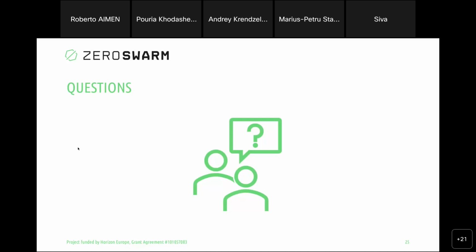Siva has a question. Just a quick thing. We have different types of industrial Ethernet protocols like Class A, Class B, Class C. For example, Class A, like EtherNet/IP, makes use of the whole 5-layer or 7-layer model, all the stacks. But Profinet RT doesn't make use of TCP/IP: once the frame arrives at layer 2, it is pushed directly to layer 7 for further processing.